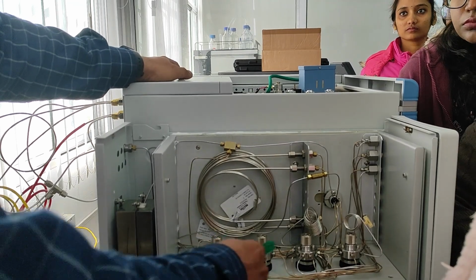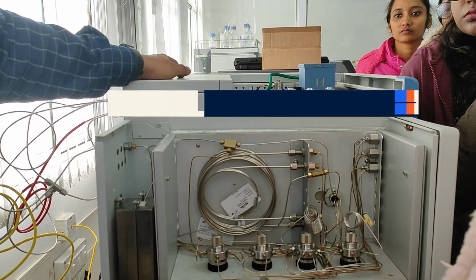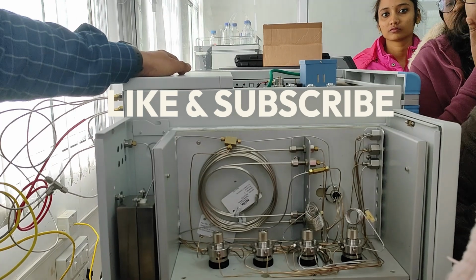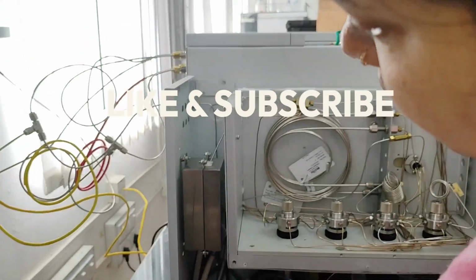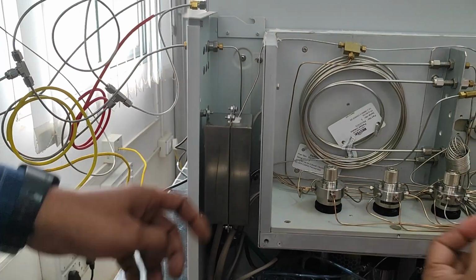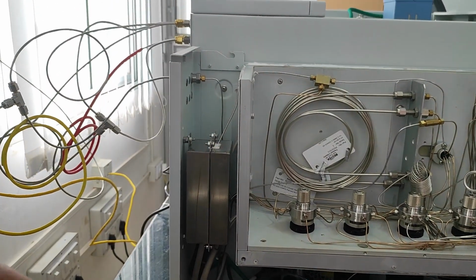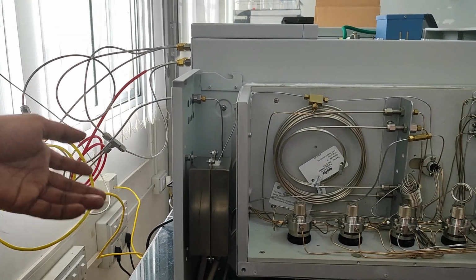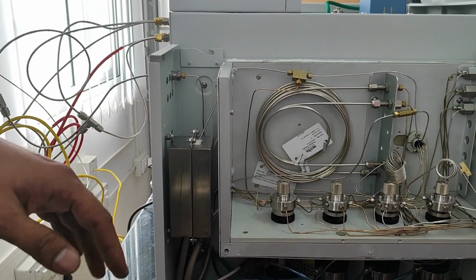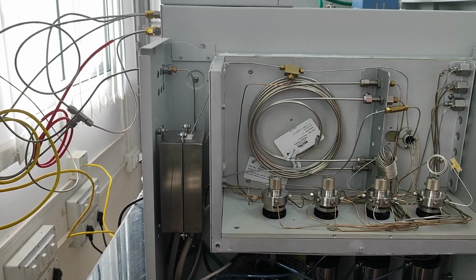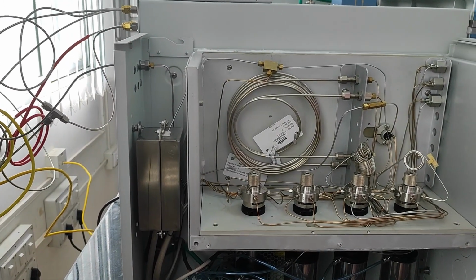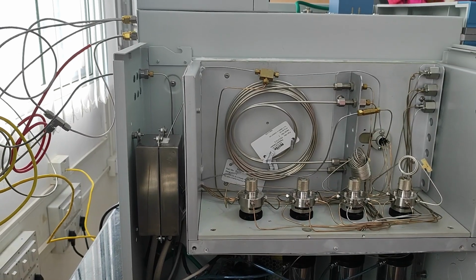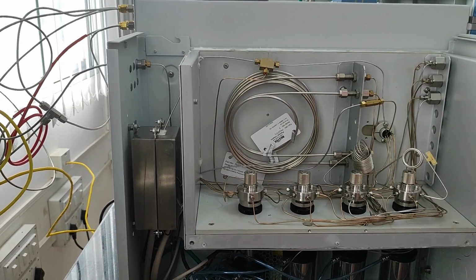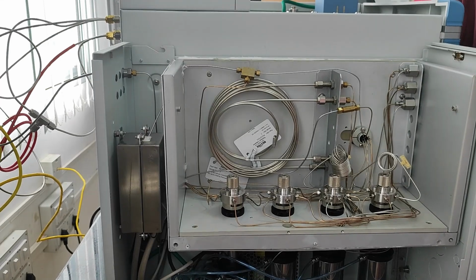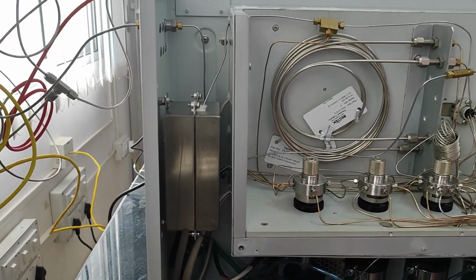All these valves cost beyond 2 lakhs. All are air actuated valves. This is the methanizer box. Inside, one tube contains nickel catalyst, and we are also giving hydrogen. Without the presence of hydrogen, it is not possible to convert CO and CO2 to methane. At the same time, it will produce H2O, water also. That water will go to the FID, and there will be no peak, no effect.